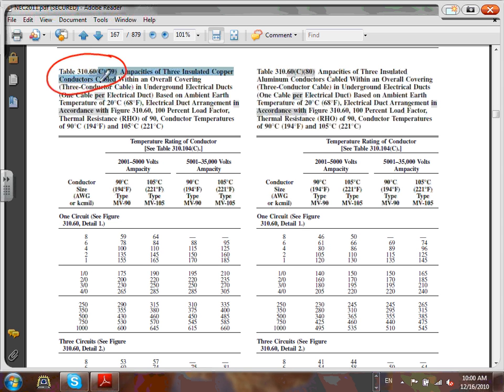Number one, what's the voltage level that we have? 4160. Because it's 4160, we're right in here. Had it been 13.8, where do you go? Right here. Then what you're going to ask me is, what insulation do I want to use? The default, unless you know otherwise, is medium voltage.